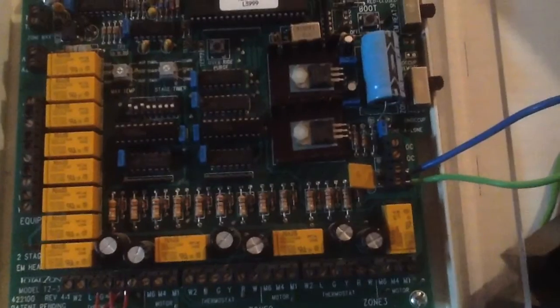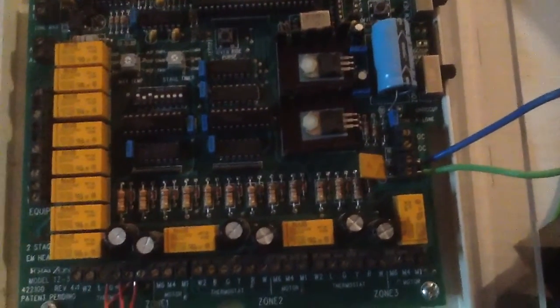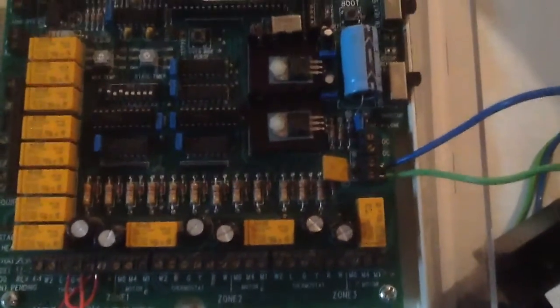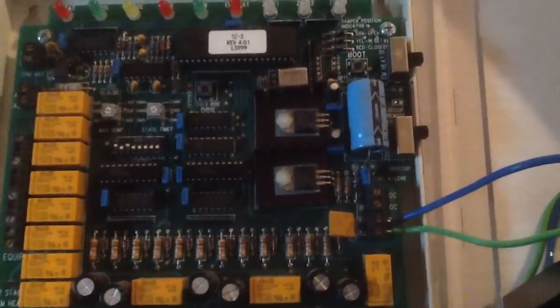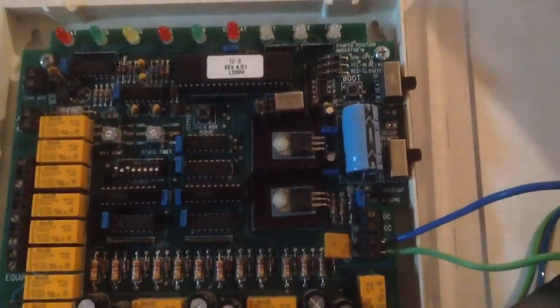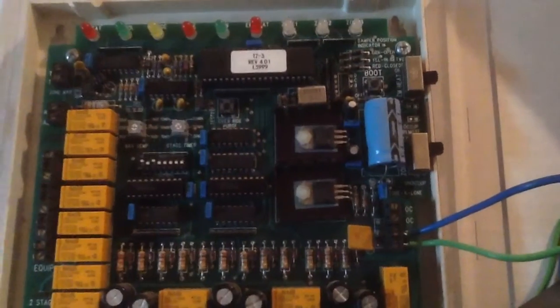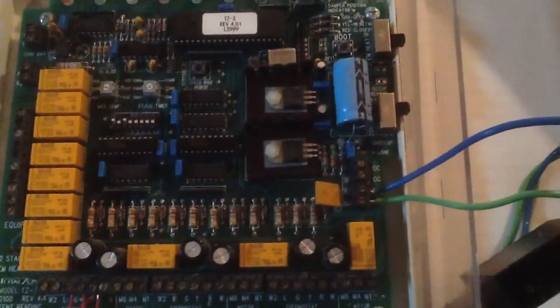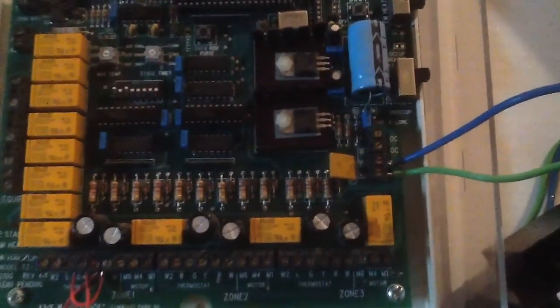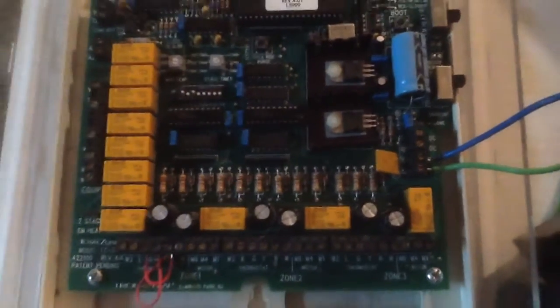And then over here, you probably can't notice the letter, but I think it has TR or something like that on the bottom where the blue and green wire go to. That's for your 24-volt connection. Typically, any zone system is going to require a secondary transformer, so you'll want to have an additional transformer inside the furnace powering up the zone board, especially if you have bigger dampers. I think EWC requires a secondary transformer if you have more than 2 10-inch dampers or a 12-inch. I usually just put a secondary transformer anyway. So that's where those 2 terminals are, that's where you power up the board. This is incoming 24-volt power to the zone board.